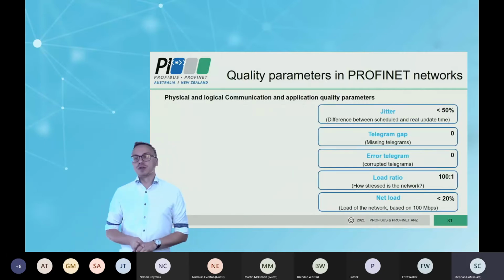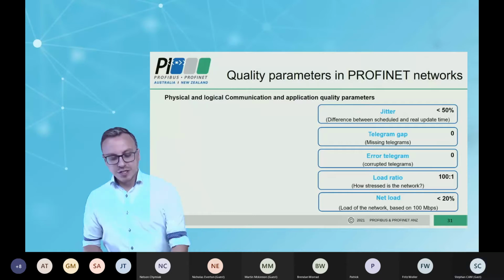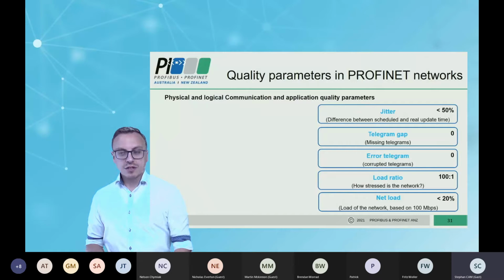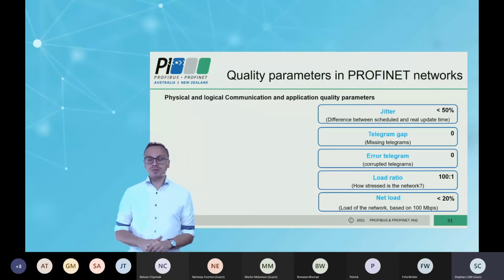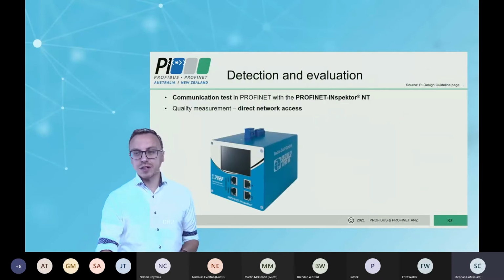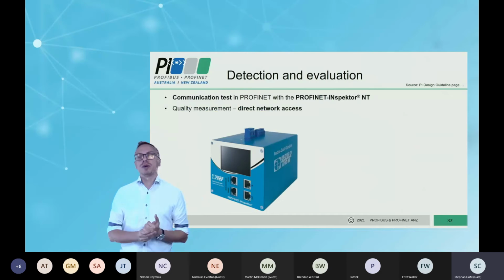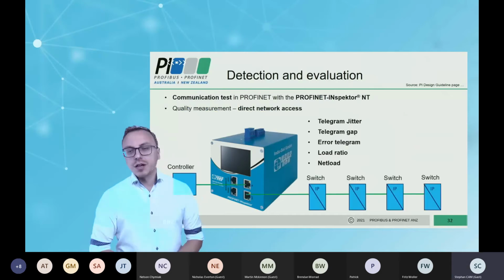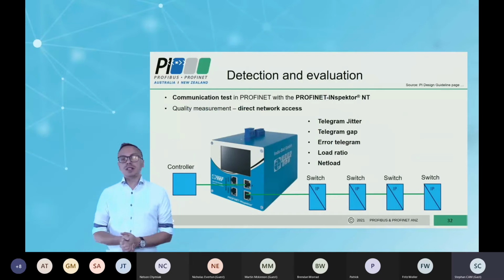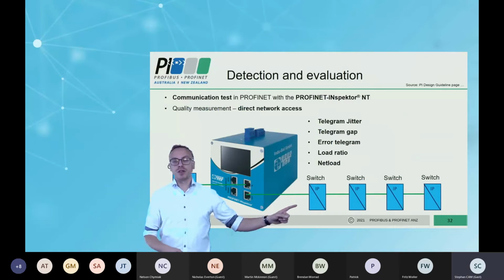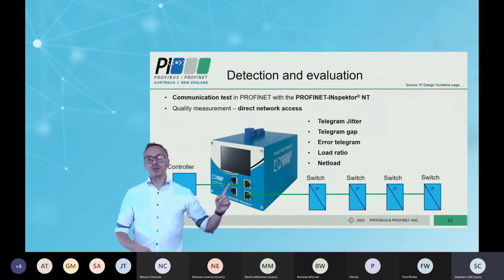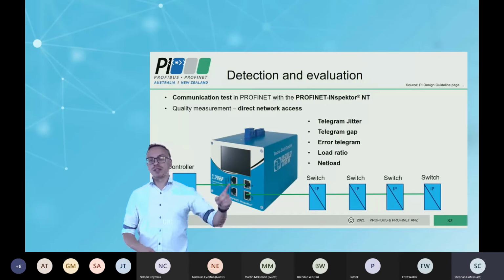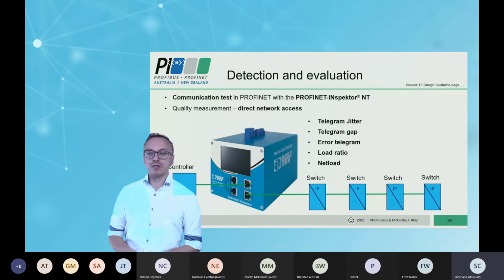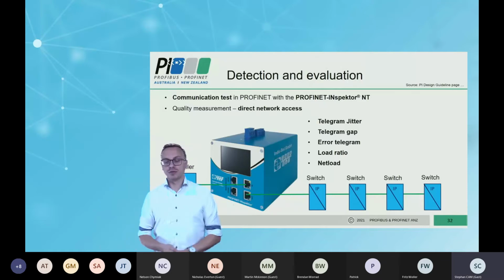Now we come to the logical values. The logical values need special hardware. You cannot read them out from the PLC, because the PLCs don't give you a network overview. For this, you normally need measurement tools like the PROFINET Inspector. If you look at the guidelines, it is recommended that you have a measurement point or a tap between the controller and the first device, for example your switch. Between your controller and your first device, you have a measurement point or the measurement tool itself. And if you are inside this connection, you can find out all these quality values very easily.